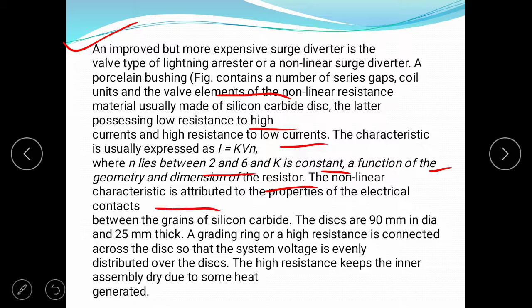It is a non-linear surge diverter. A porcelain bushing, as in the figure, contains a number of series gaps, a coil unit, and the valve element of non-linear resistance. The material is usually made of silicon carbide discs, offering low resistance to high current and high resistance to low current. The characteristic is expressed as I equals K V to the power N, where N lies between 2 and 6 and K is a constant, a function of the geometry and dimensions of the resistor. The non-linear characteristic is attributed to the property of the electrical contacts between the grains of silicon carbide.